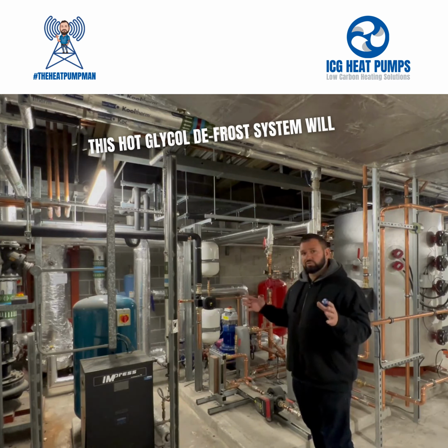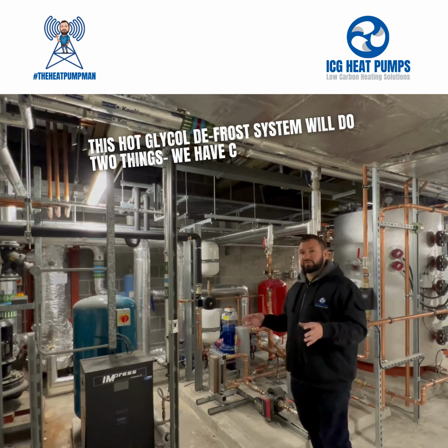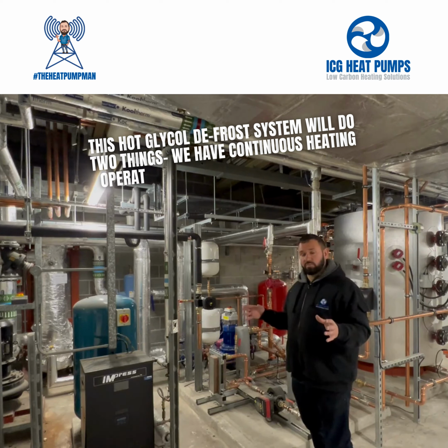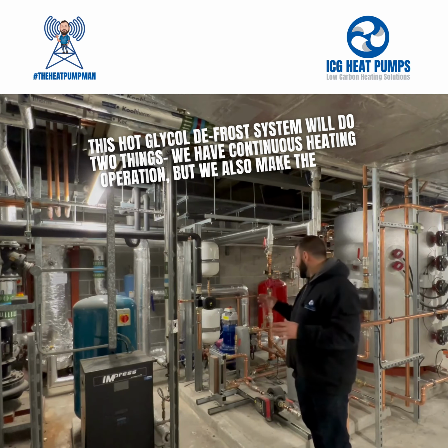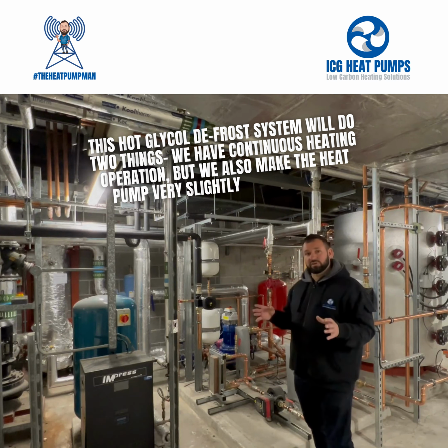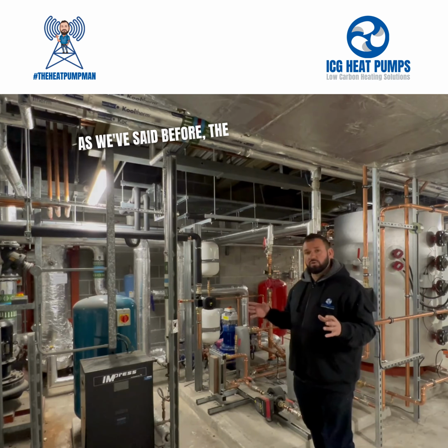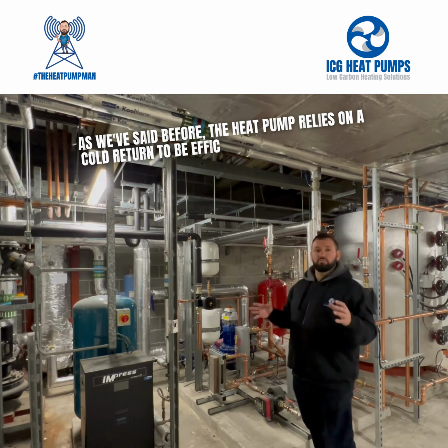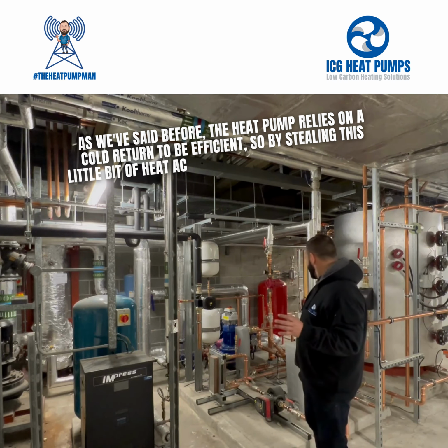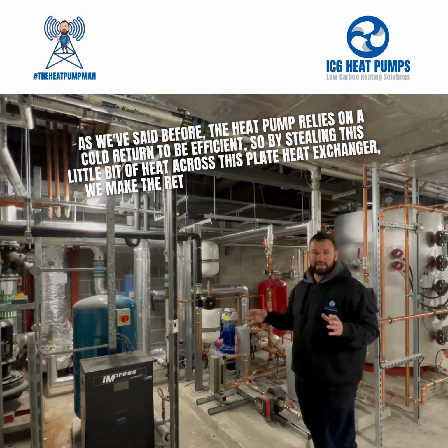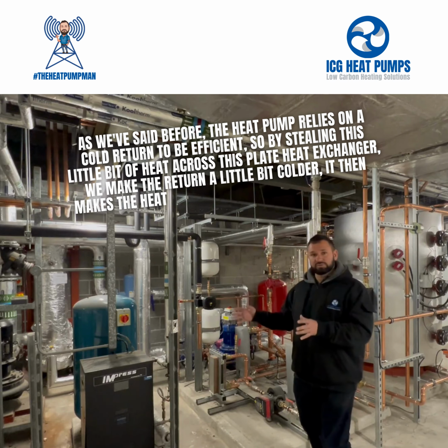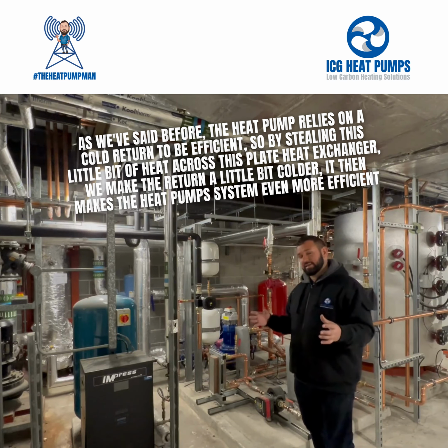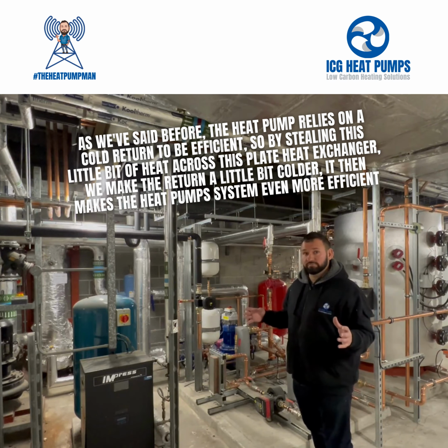This hot glycol defrost system, we do 2 things. We have continuous heating operation, but we also make the heat pump very slightly more efficient. As we said before, the heat pump relies on a cold return to be efficient. So by stealing this little bit of heat across this plate heat exchanger, we make the return a little bit colder, and it makes the heat pump system even more efficient.